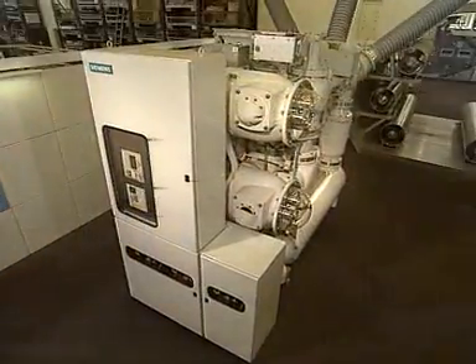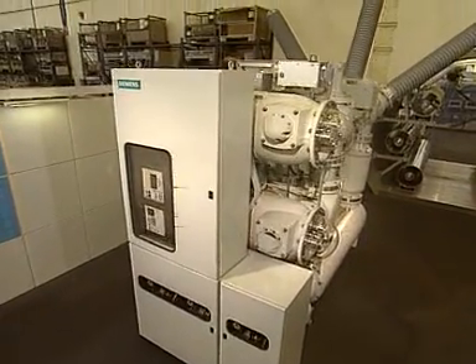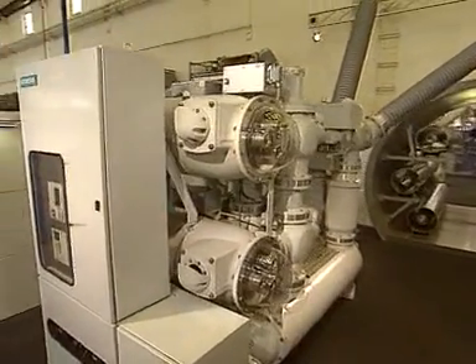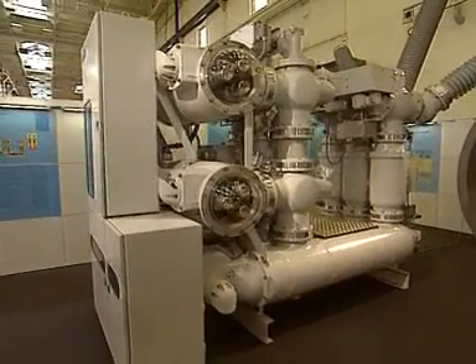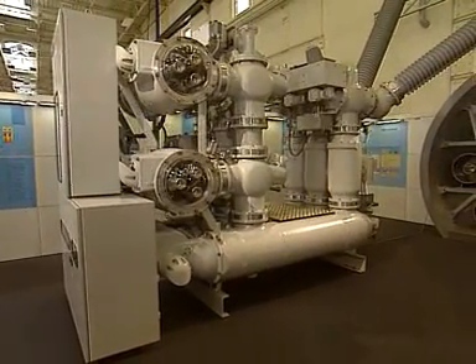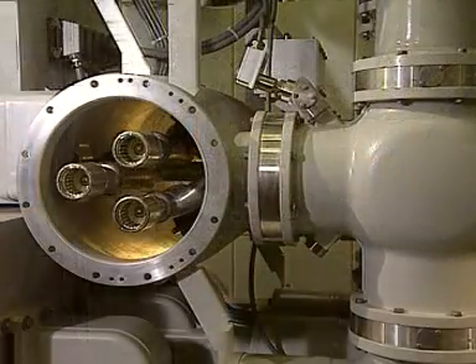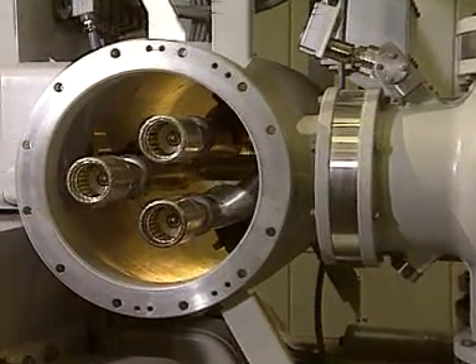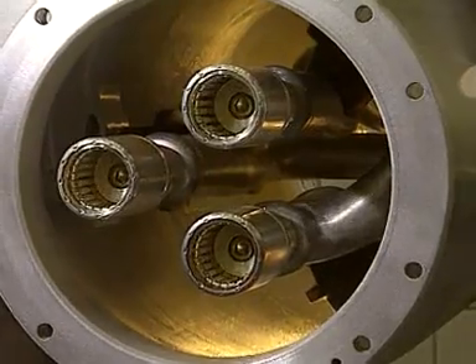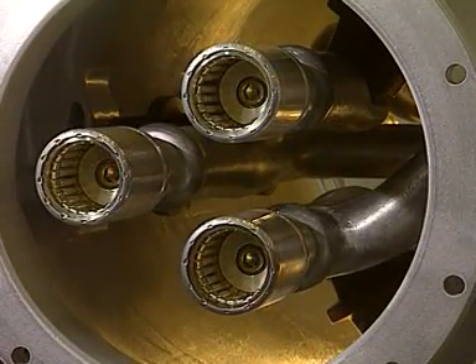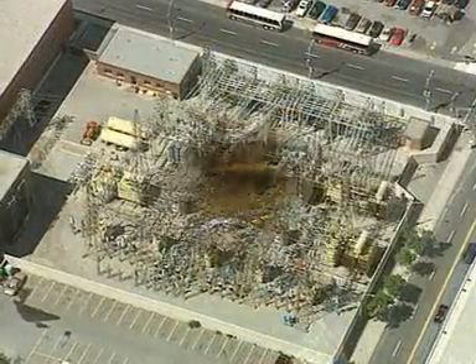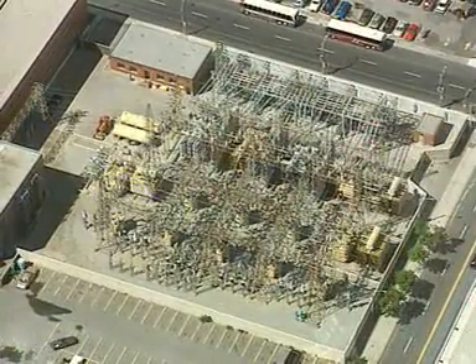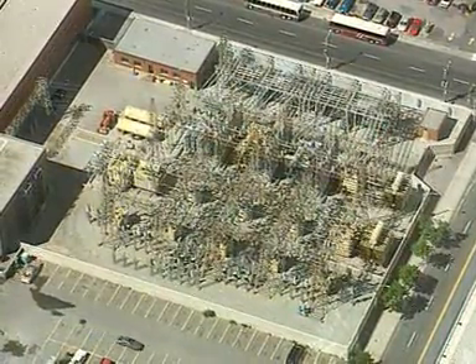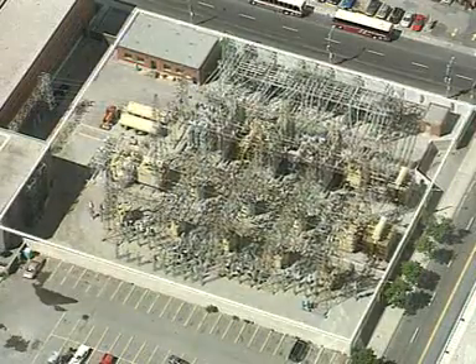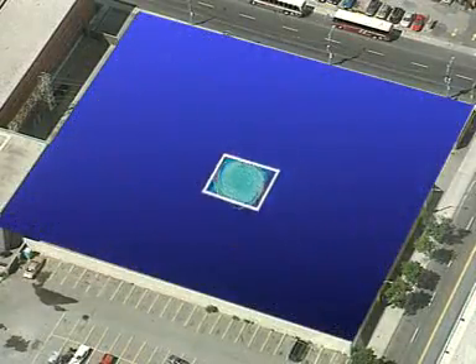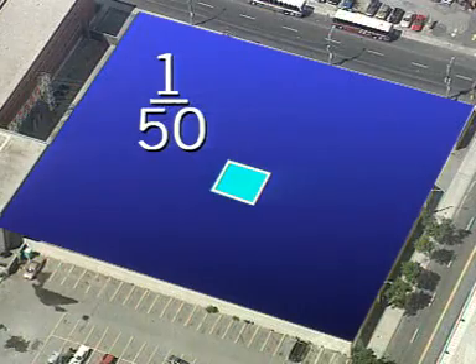This is why Siemens has been utilizing the good insulation properties of SF6 gas in metal-enclosed high-voltage switchgear since 1964. Continuous enhancement of enclosure shapes and production methods has enabled triple pole encapsulation of the busbar in the narrowest of spaces, even at 245 kilovolts. Result: this extensive outdoor substation for 245 kilovolts can be replaced by a metal-enclosed SF6 insulated system that needs only 1/50th of the previously required floor space.